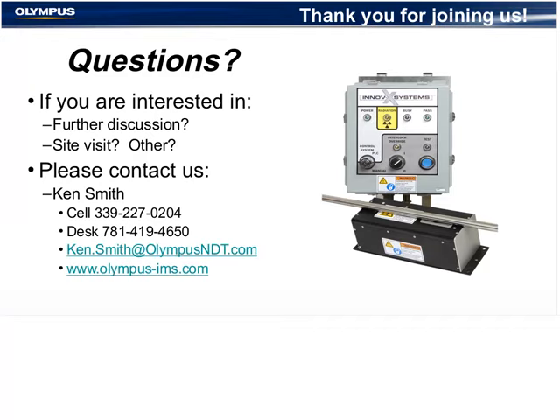One of the questions that came in is, is the radiation level dangerous? There's no amount of radiation that is good for anybody or recommended. It is regulated, and all the installations use shielding in some manner depending on their layout and their state requirements. Sometimes there's a metal or a leaded Lexan enclosure that's put around the probe head, just a small enclosure. Sometimes all that needs to be done is that the area has to be set up so that people can't get near the system. But it is an open beam system, and the radiation has to be managed, and we provide guidance for that. It's a routine thing.